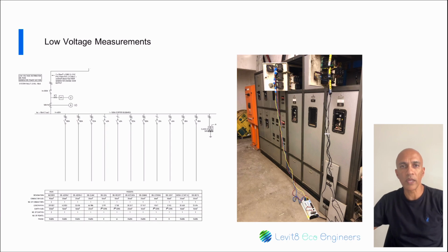We will also look at the correct points for current measurements to get accurate readings of the full load being consumed. Let us first discuss low voltage measurements, which is going to be the more likely scenario for most people. Now, this typical low voltage single line diagram gives a good starting point of where you would want to connect your voltage leads and current clamps.